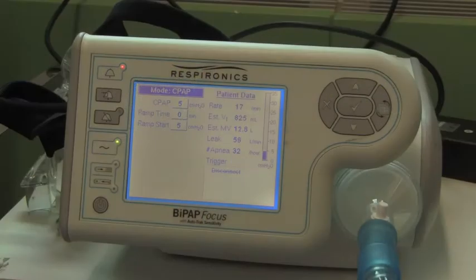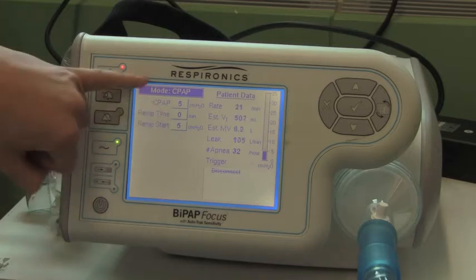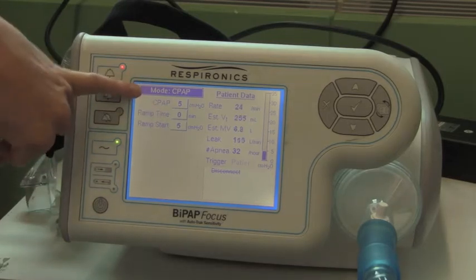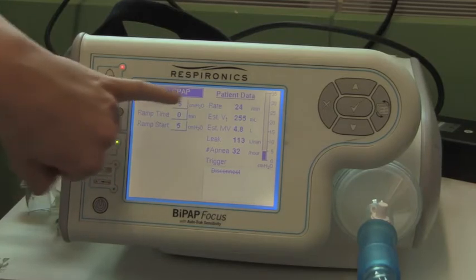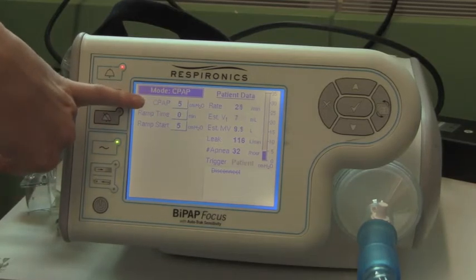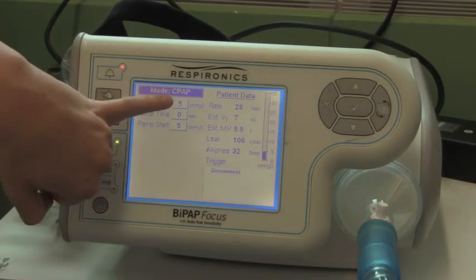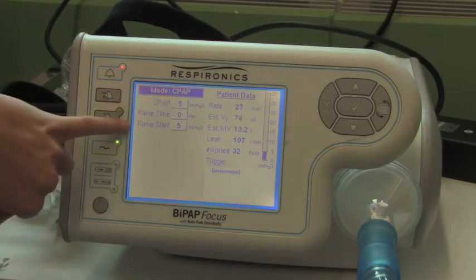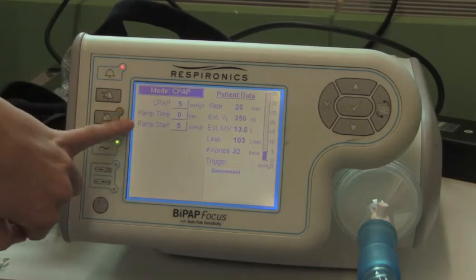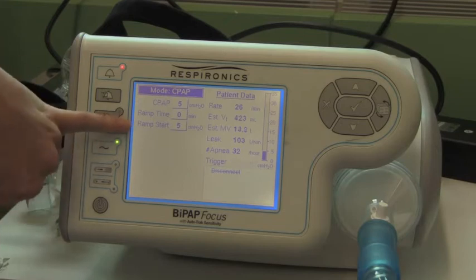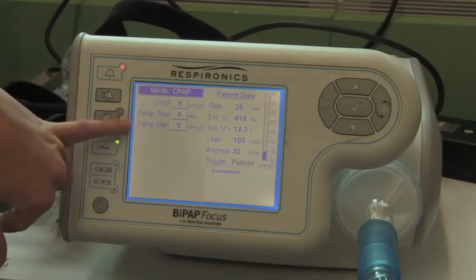This is a non-invasive ventilatory device that can deliver different support modes. This mode is set to CPAP. This bit here, that's what the pressure is set at, so this is set at 5. This ramp time and ramp start is not used in acute settings. It will be discussed further in the teaching session.